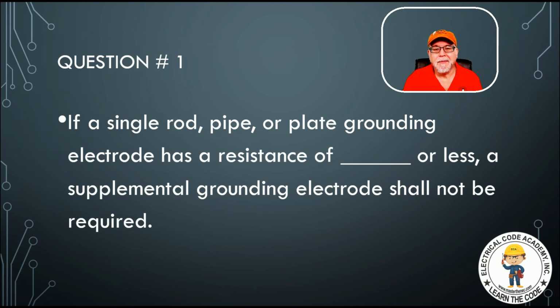That wouldn't make sense. But you can use any of the others. Now the water pipe ground gets supplemented, but the other electrodes in our list that get supplemented are ground rods, pipes, and plates. Now, there is an exception to this rule that says you don't have to supplement a single ground rod, pipe, or plate if you can show a resistance of blank or less. If you can do that, then you don't have to supplement it.